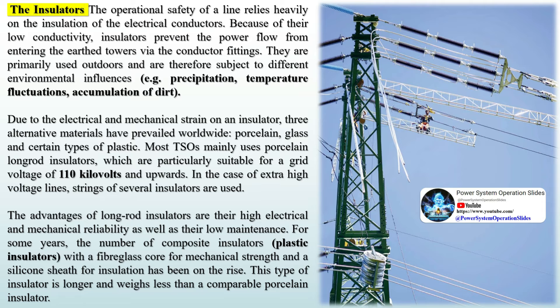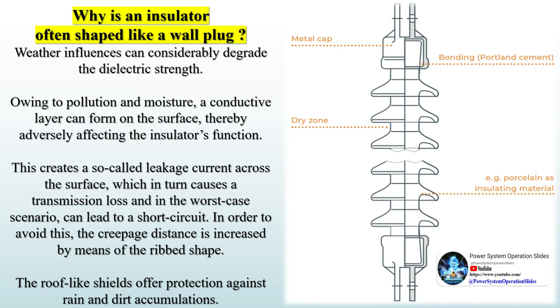In the case of extra-high voltage lines, strings of several insulators are used. Why is an insulator often shaped like a wall plug? Weather influences can considerably degrade the dielectric strength. Owing to pollution and moisture, a conductive layer can form on the surface, thereby adversely affecting the insulator's function. This creates a so-called leakage current across the surface, which in turn causes a transmission loss and, in the worst-case scenario, can lead to a short circuit. In order to avoid this, the creepage distance is increased by means of the rib shape.